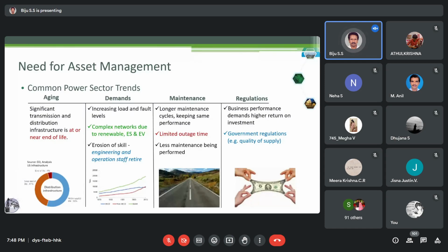Permit to manage work for maintenance is a bit difficult to get nowadays for the extra high voltage system. So outage time is less. So because of that, less maintenance is being carried out. Again, the assets have become susceptible to failure.